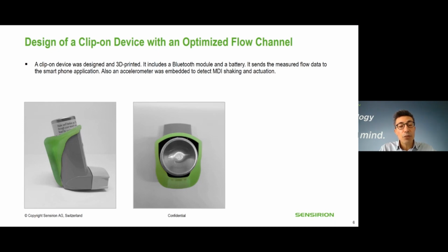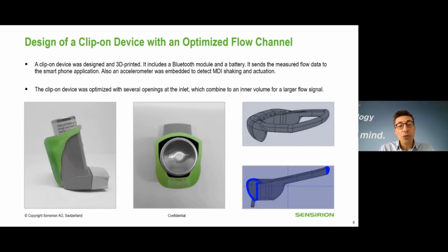The clip-on device transmits the results to a smartphone application that processes the data and generates the flow profile and lung function. We can see here the side and top views of the green clip-on device attached to the inhaler. By zooming into the top view, we can see the optimized design of the flow channel with 4 openings for a larger flow and therefore a higher sensitivity of the measurement.